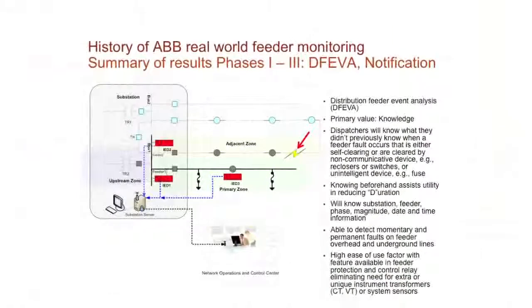The good news is we had a lot more primaries than anything else, but in the adjacents we were still able to say the different types of events from this list. So it's sort of an adjacent zone, but I'm still going to say it was a breaker failure, a reclose into the fault, a switching transient, or a cable fault. But it's not my feeder, it's the feeder next to me. That's what this means, the different events for an adjacent zone.